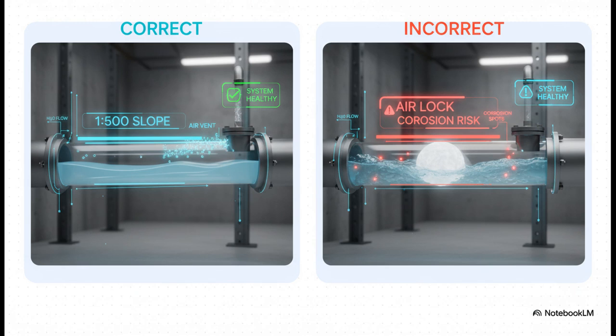Okay, now here's a detail that seems incredibly tiny, but trust me, it is a game changer. Every single horizontal pipe has to be installed with a slope. We're talking a 1 to 500 slope. It's almost impossible to see with your own eyes, but that tiny incline lets air, which is the absolute enemy of a water system, get pushed out properly. If you install the pipes perfectly flat, you trap air bubbles, and that leads to gurgling noises, corrosion, and just awful performance. So the lesson here is simple. Gravity is your best friend.